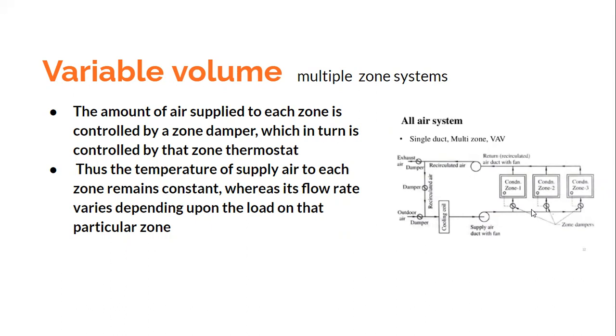These dampers are then controlled by a thermostat. Depending upon the temperatures to be maintained, your damper position could be set. So these are the controls. You can set the damper positions by sensing the temperatures in the zones. The temperature of supply air to each zone remains constant, whereas the flow rate varies depending upon the load. So you are supplying a constant temperature of supply air. However, what you are changing is the flow rate, depending upon the cooling load in these zones.